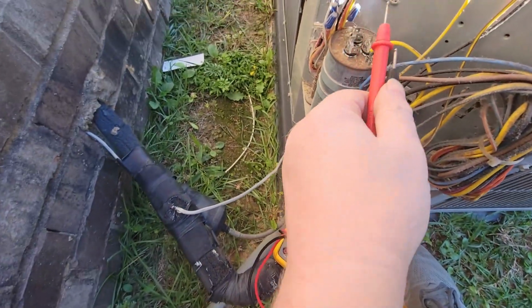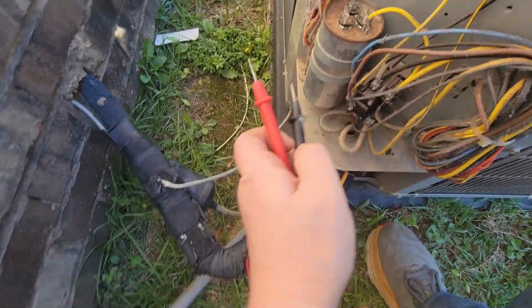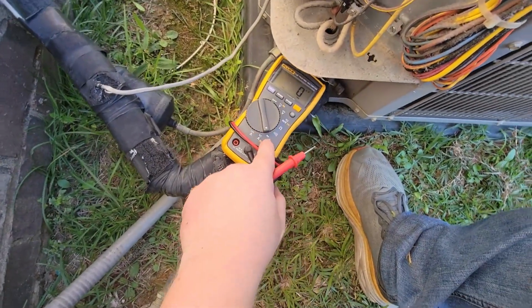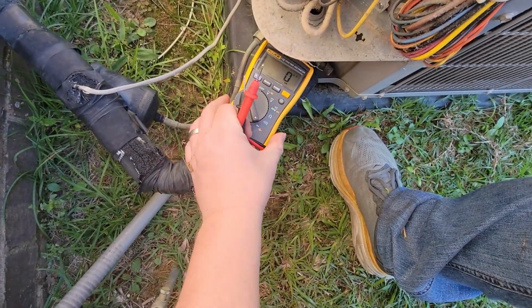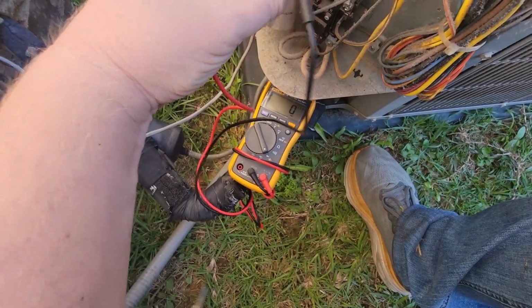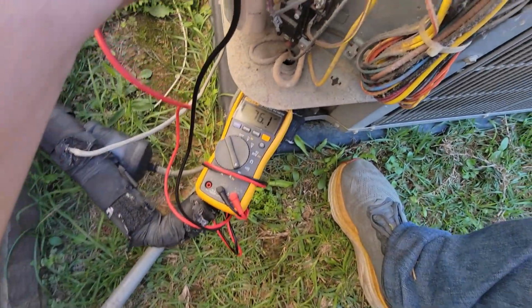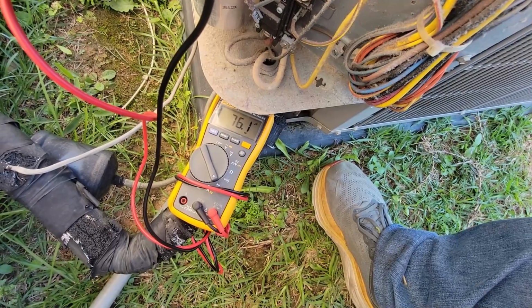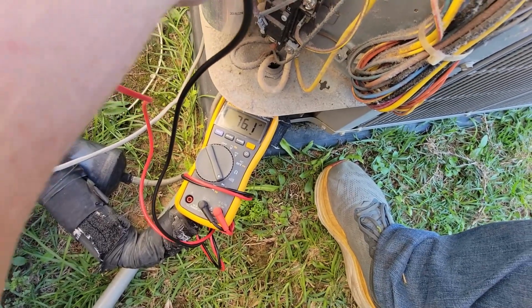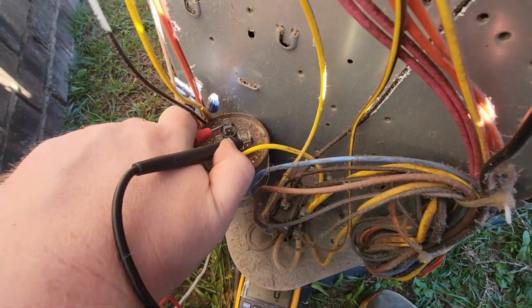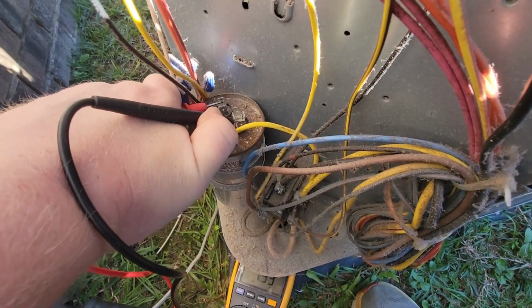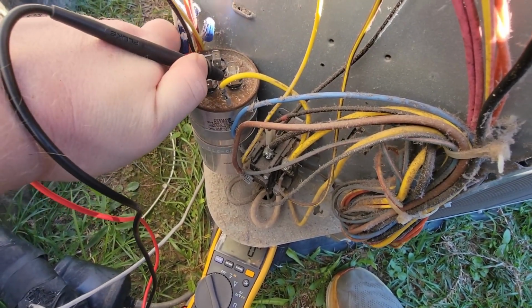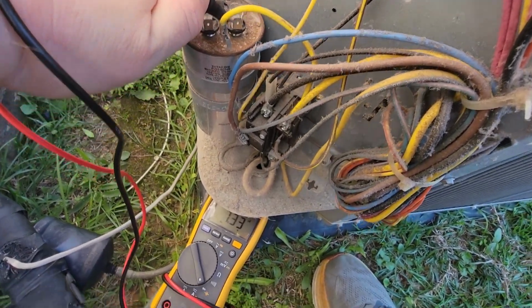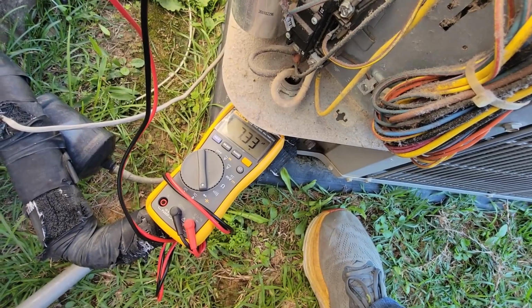So we got a little swing there that we can look at. Let's see. First one's going to be 80. I'll set this to diode. I hit that special function key that puts it into a microfarad reading, or the ability to read capacitance. And I'm going across those two terminals. We see we got 76.1. Now I need to come across the other terminal, this one up here, where the yellow was at. So we're now brown and yellow, and we got a reading of 7.33.